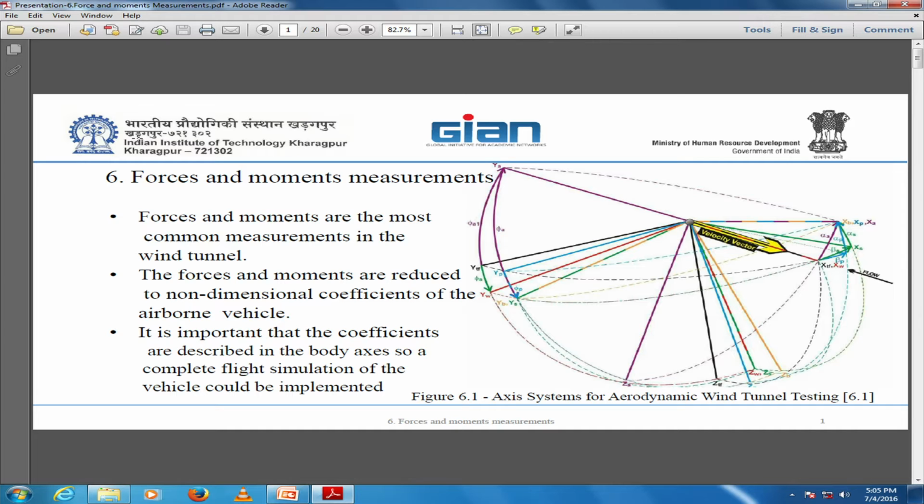This is the reason why you cannot commit in such a system to be more accurate than what it says now, one tenth, because it depends on the balance that you are calibrating. If you are given a balance to calibrate, you don't know where it was produced, how accurate it is, or the age of that system, and it can be very problematic.